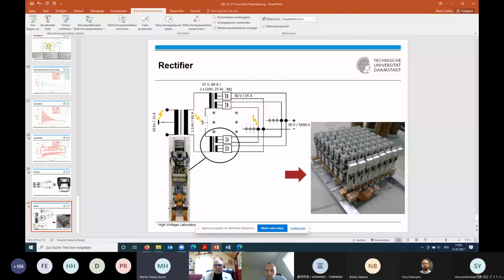This is not possible. So we are using a concept with several modules in parallel. We get our high frequency signal, which is around 25 V and 60 amps at maximum. Then we use several transformers with the primary windings in serial connection, and the secondary windings connected in parallel. By that, each transformer only gets a small amount of the rating, and also on the secondary winding only a small amount of rating. But by connecting them together, you get the overall high rating you want. Each secondary winding of the transformer has an M2 rectifier, and this M2 rectifier is feeding a busbar, and this busbar then collects all the currents together.